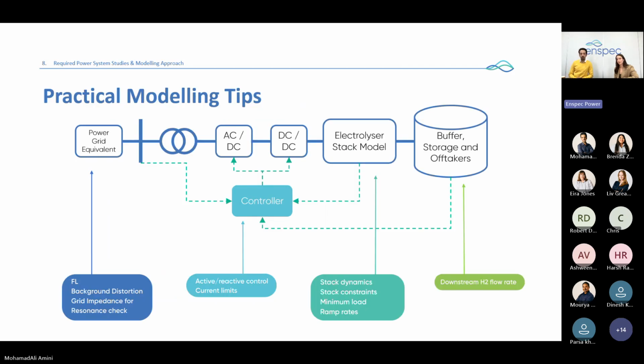In terms of modeling tips, to develop an appropriate model for the study, it needs to encompass different components. For example, an equivalent model for the power grid needs to consider the fault level, background distortion, grid impedance for any probable resonance check, and from the controller itself, active and reactive control, and also current limits need to be considered. For the electrolyzer itself, stack dynamics, stack constraints, and minimum load and ramp rate need to be considered in the model, and also the downstream hydrogen flow rate needs to be considered.